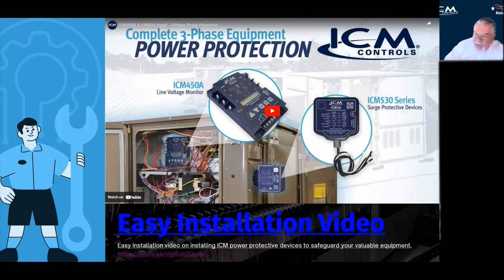So the good thing about the line monitor is it does protect you from over and under voltage. Brownouts are equally dangerous to equipment, but the spikes, the line monitor can't really do much about that. So the surge protection device is very, very critical, and we're going to spend a little bit of time talking about that going forward. But nice installation video there on how to install those.